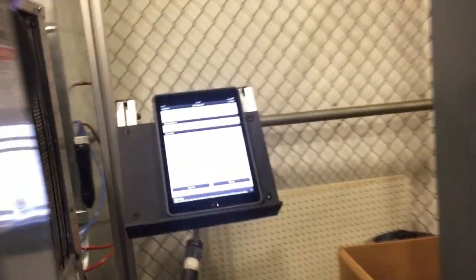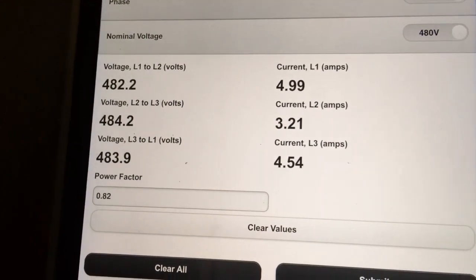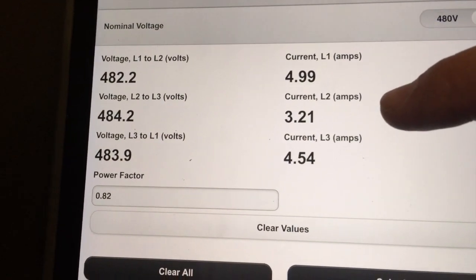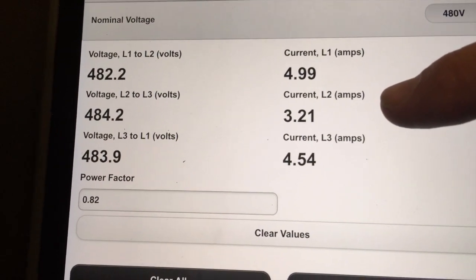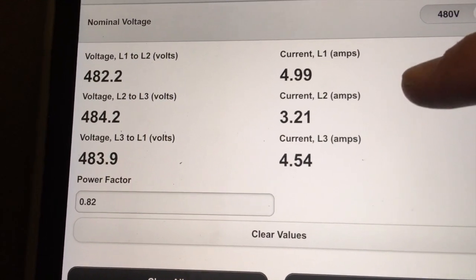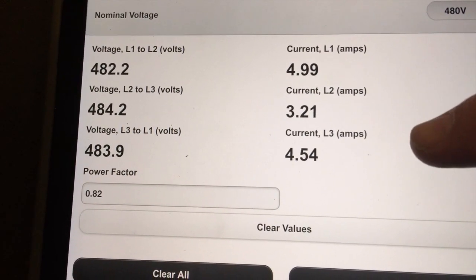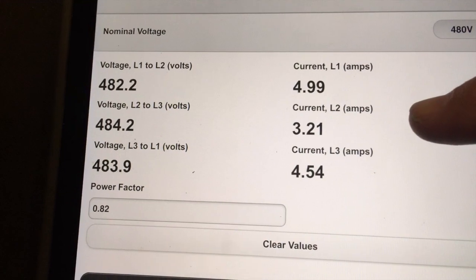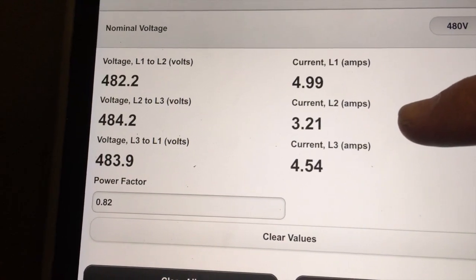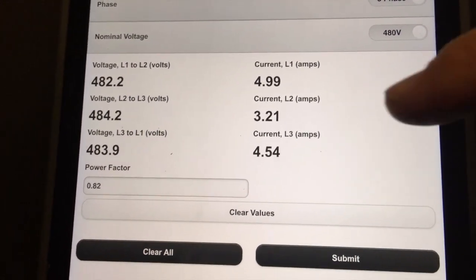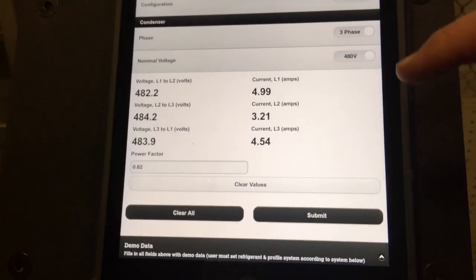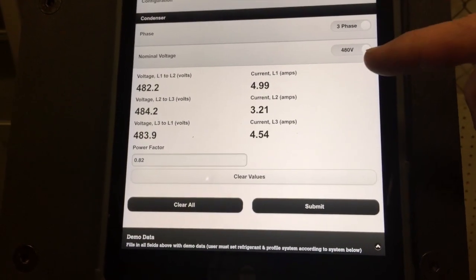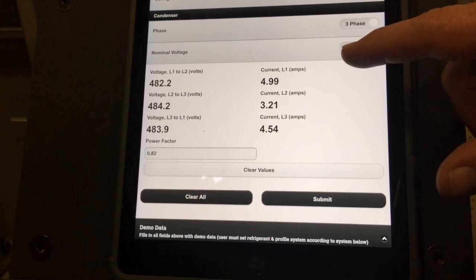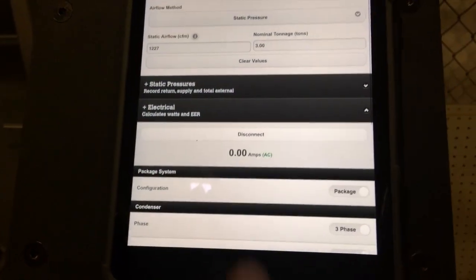So if I come back over here to my iManifold application, you can see my voltages and my currents. The reason that we have this current imbalance here is because this system has an ECM blower in it, and they're robbing 2 legs for a transformer to power the ECM, so the center leg doesn't see any of that current, and that's what we're seeing. Later in the application, I'll show you how we calculate the current or the voltage imbalance in the application. So the last thing we need in our measurements here, we'll just close electrical, is our static pressure.